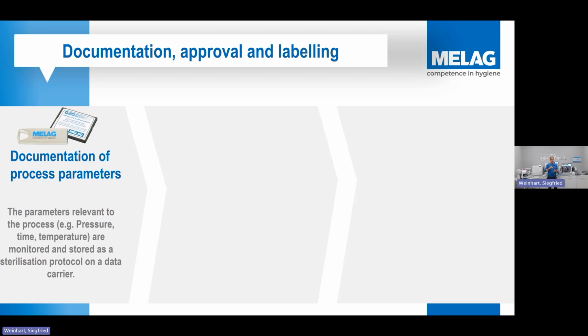So it's looking at time, temperature, pressure. It's giving it a date stamp. It's telling you what time you started the cycle, what time the cycle finished. It'll note the serial number of the autoclave. It'll note the cycle number of the autoclave. Okay, and then it'll say on there, did it pass or did it fail? And that gets recorded on the data logger. So that's the first element, keeping those 2 years for England and Wales, lifetime of the equipment for Scotland, minimum 8 years for the Republic of Ireland.